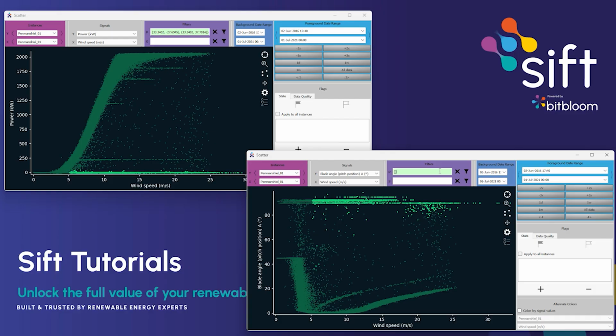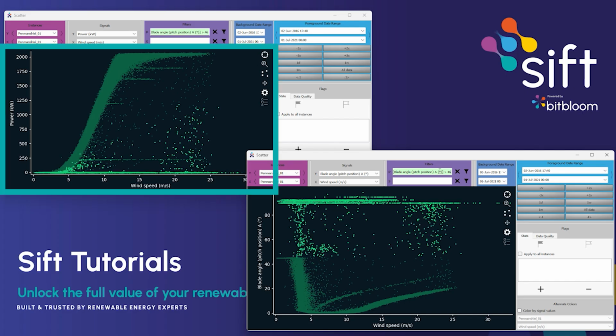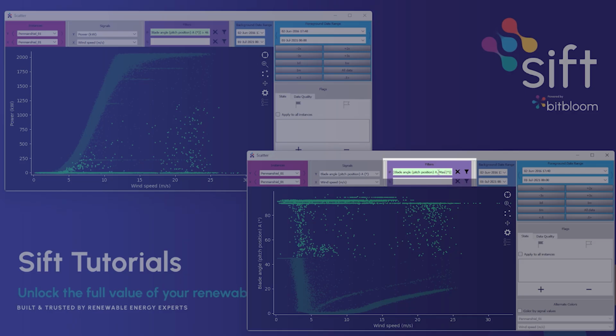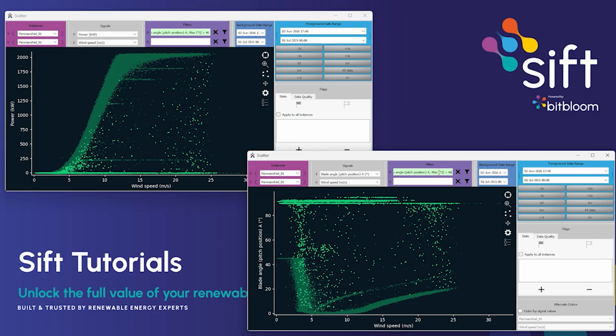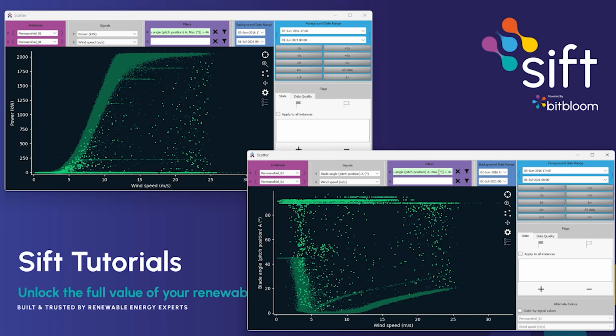If we filter the data for pitch angle above 46 degrees, you can see that this highlights downtime on the power curve, but also transitional points, where part of the 10-minute data is downtime. We can capture more transitional points by using pitch max. Not all points on the power curve are highlighted by this filter. Most of the remaining points under the power curve are in a different operational mode. This is one example of how using turbine control data allows us to clearly differentiate between operational modes.